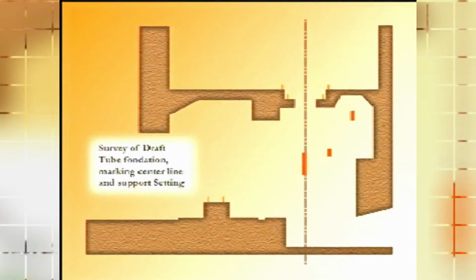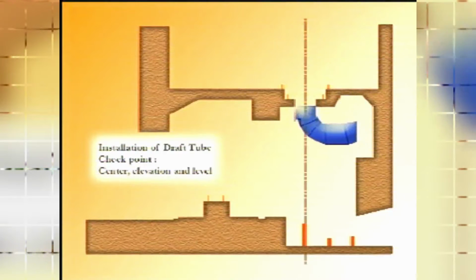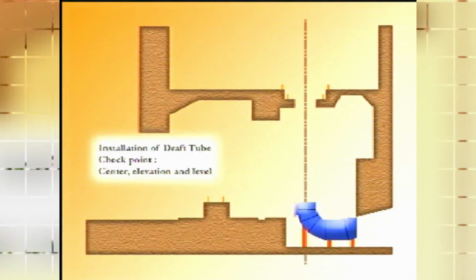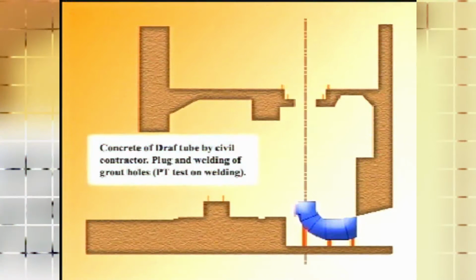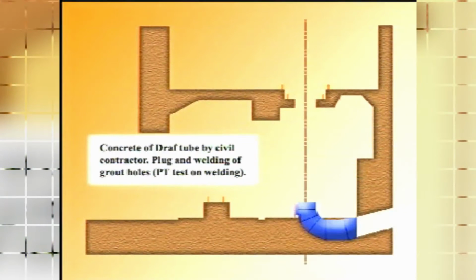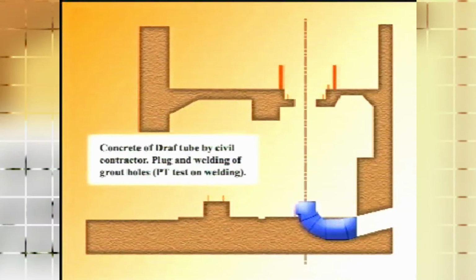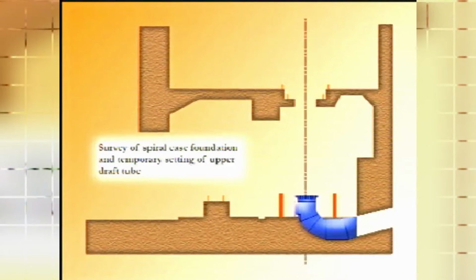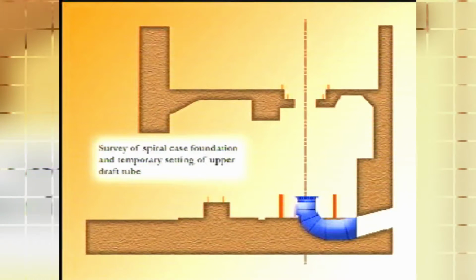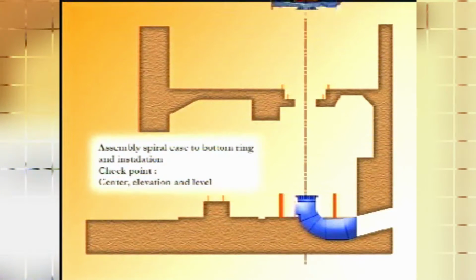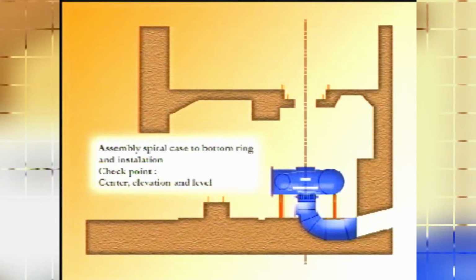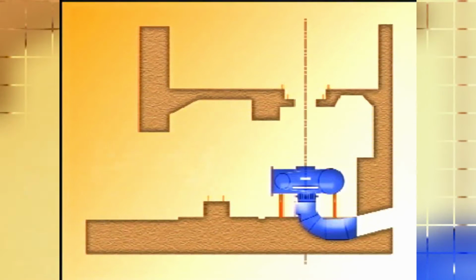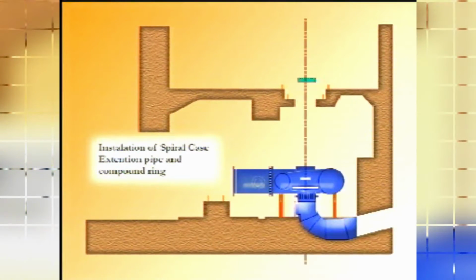Survey of draft tube foundation marking center line and support setting. Installation of draft tube. Checkpoint: center, elevation, and level. Concrete of draft tube by civil contractor, plug and welding of grout holes. PT test on welding. Survey of spiral case foundation and temporary setting of upper draft tube. Assembly of spiral case to bottom ring and installation. Checkpoint: center, elevation, and level. Installation of spiral case, extension pipe, and compound ring.